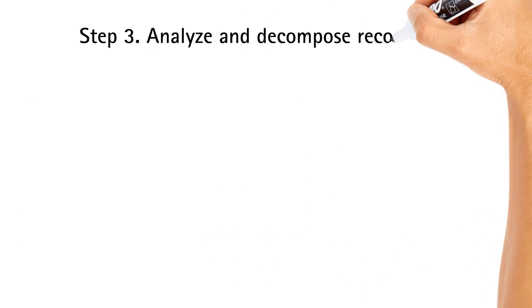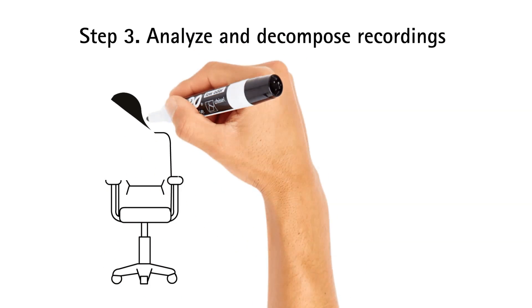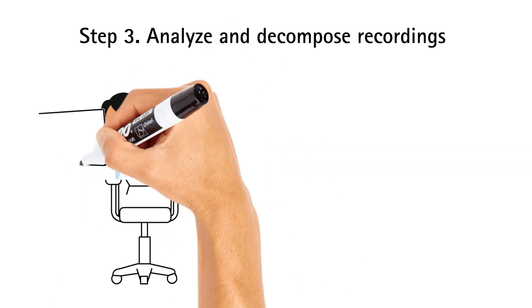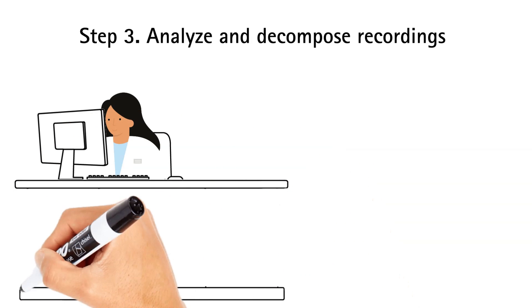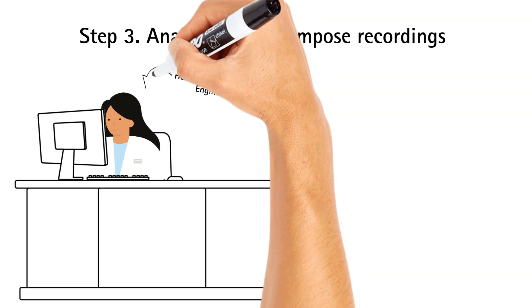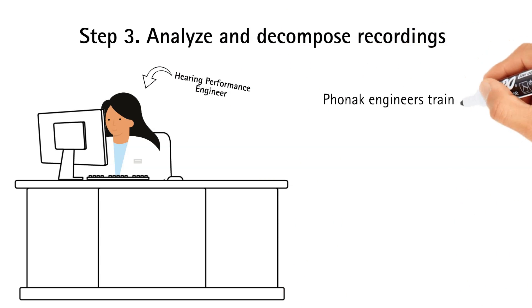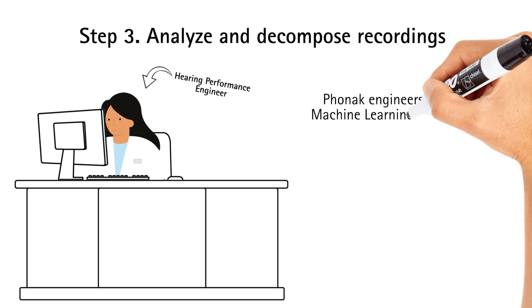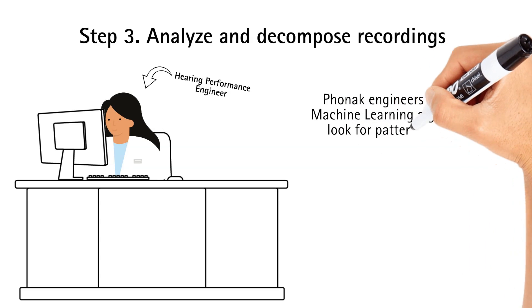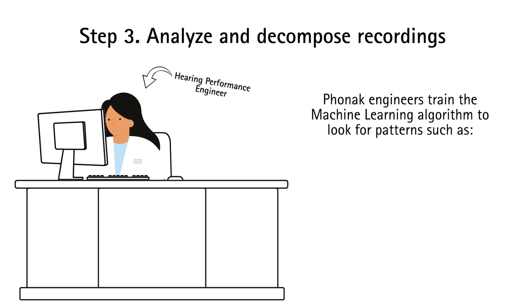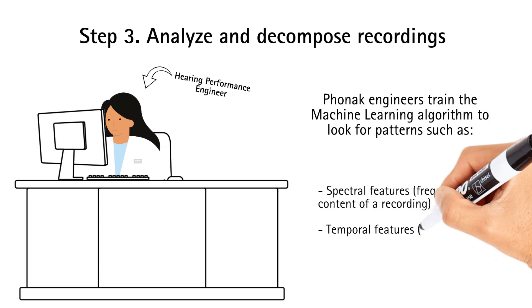Step 3 involves the analysis and decomposition of the recordings. Phonak hearing performance engineers train the machine learning algorithm to discern specific patterns within the audio signals of the recordings, so they can accurately and precisely understand each environment in the recording. These patterns can be spectral or temporal in nature, and help the machine learning algorithm determine each environment captured in the recordings. Spectral patterns indicate the frequency content typical of certain environments, while temporal patterns refer to changes in intensity and dynamics of the sound captured in the recording.